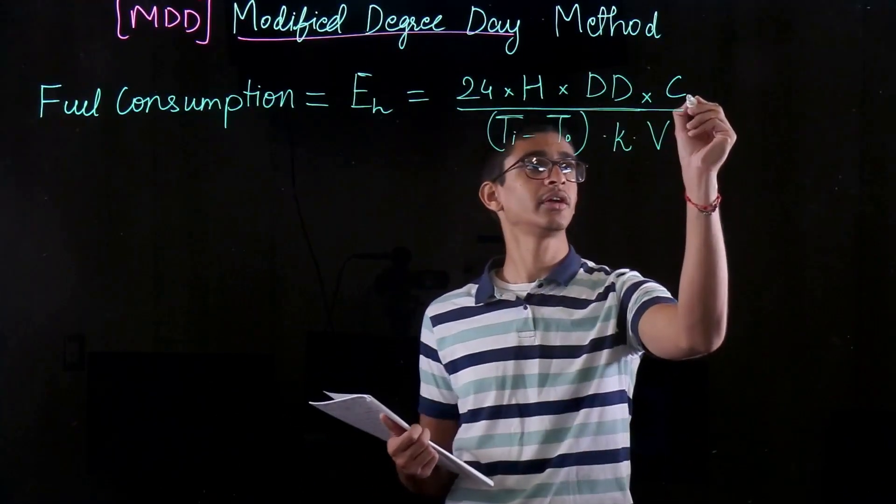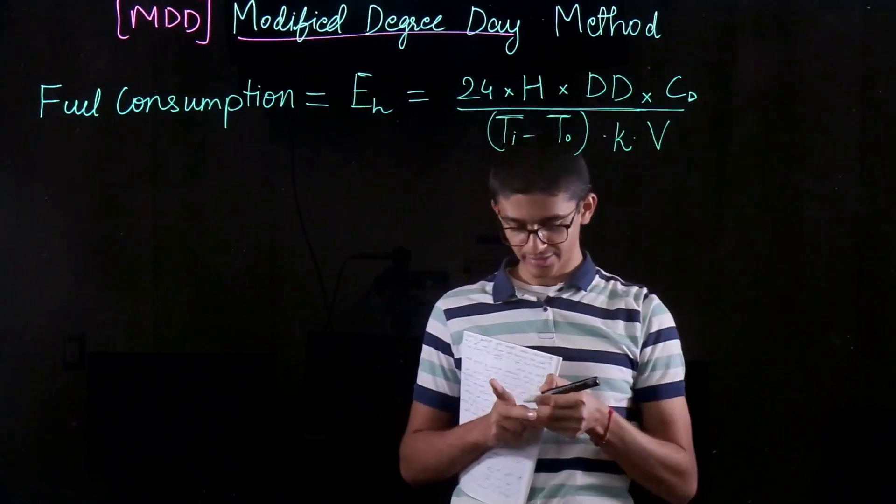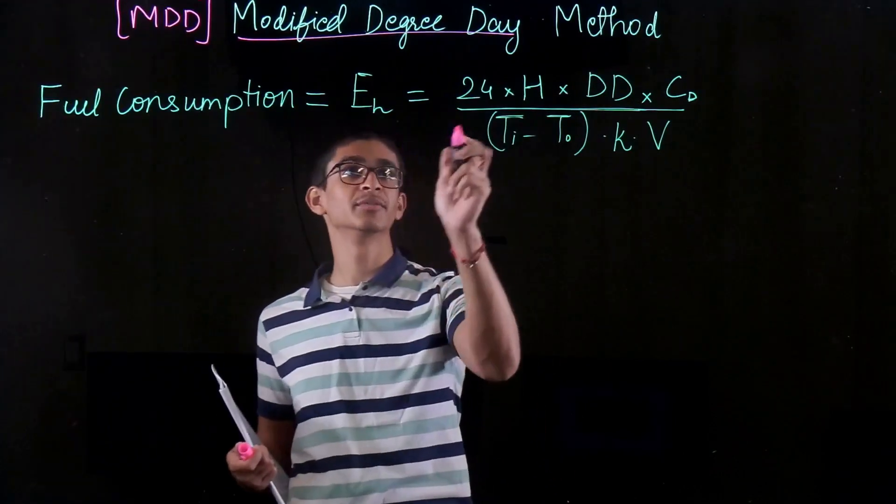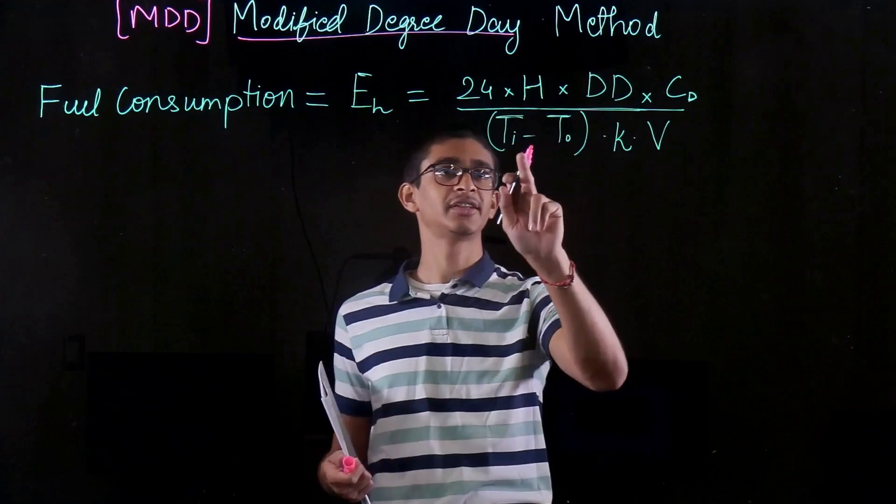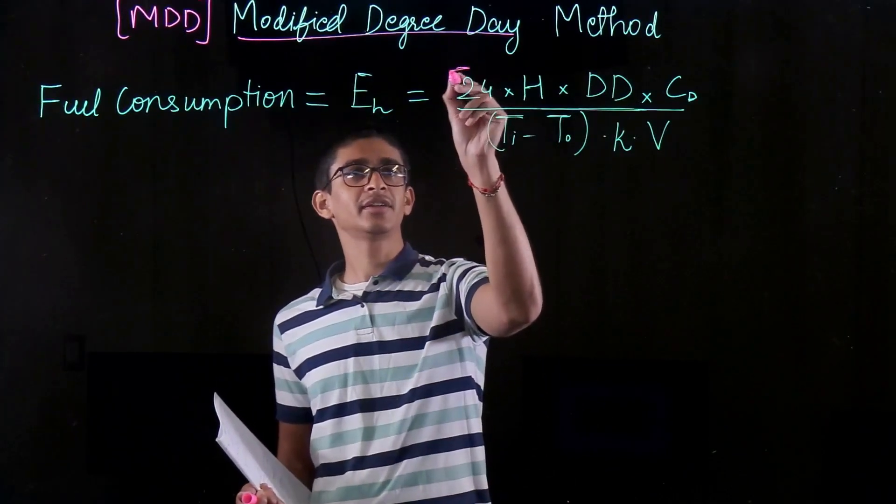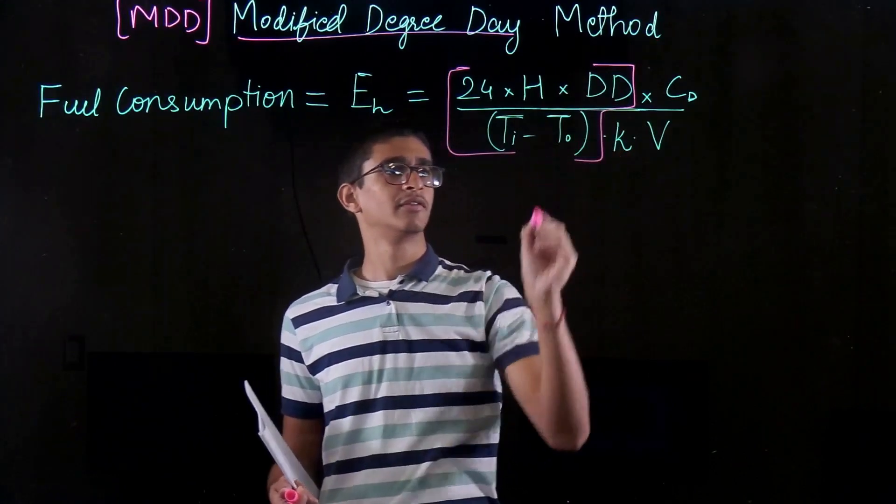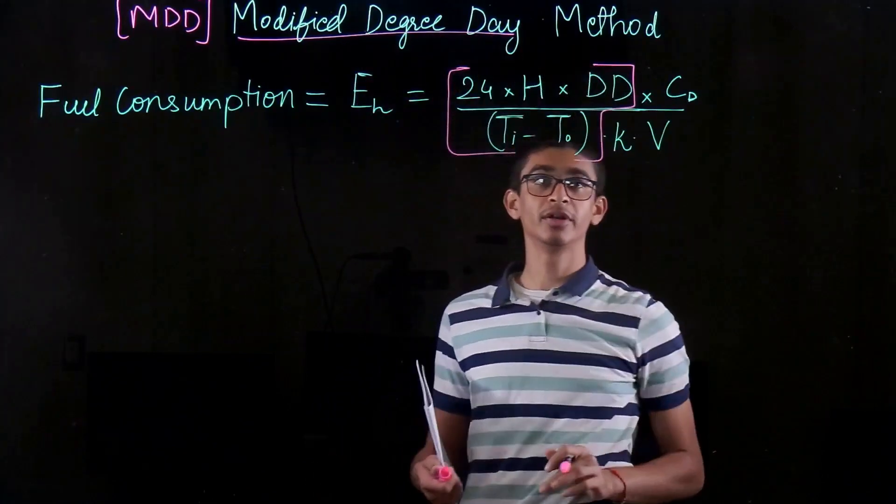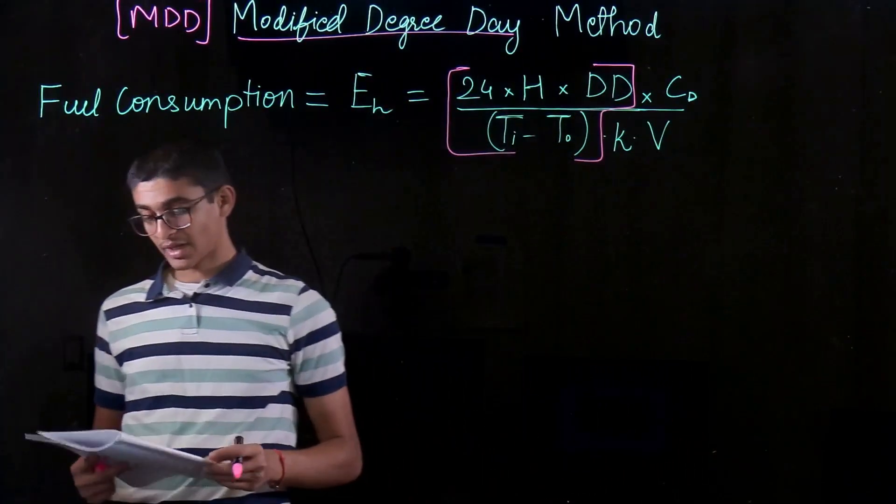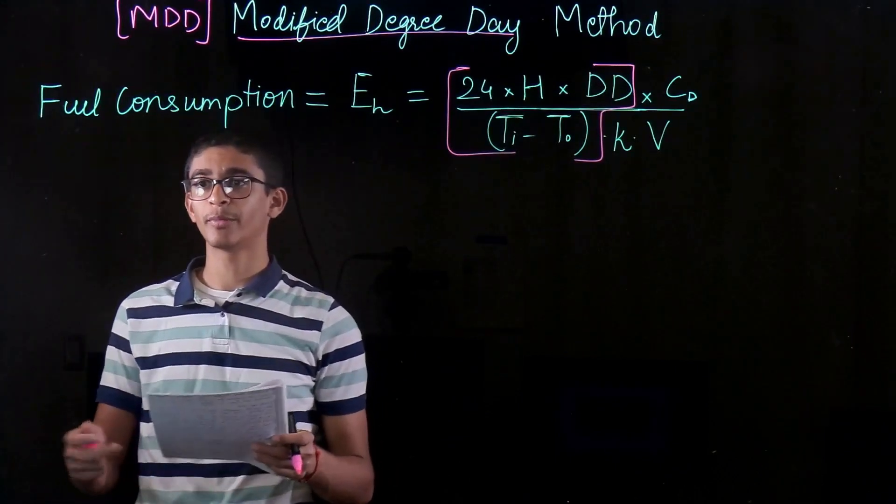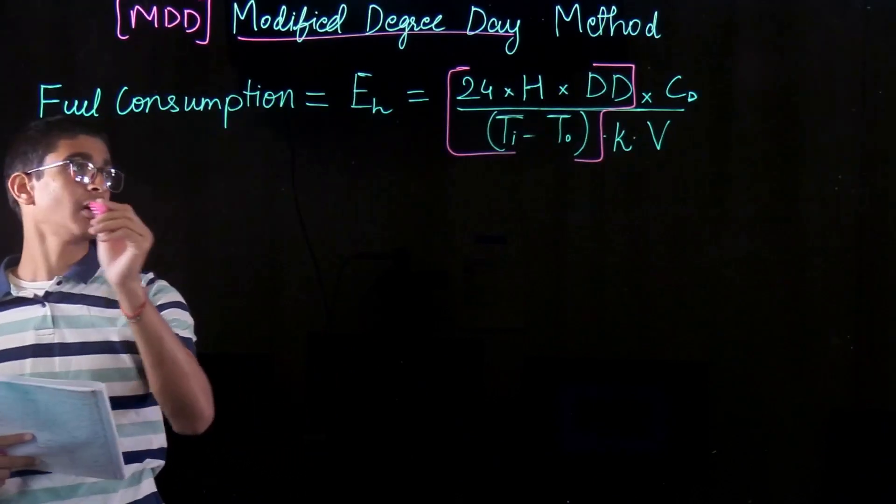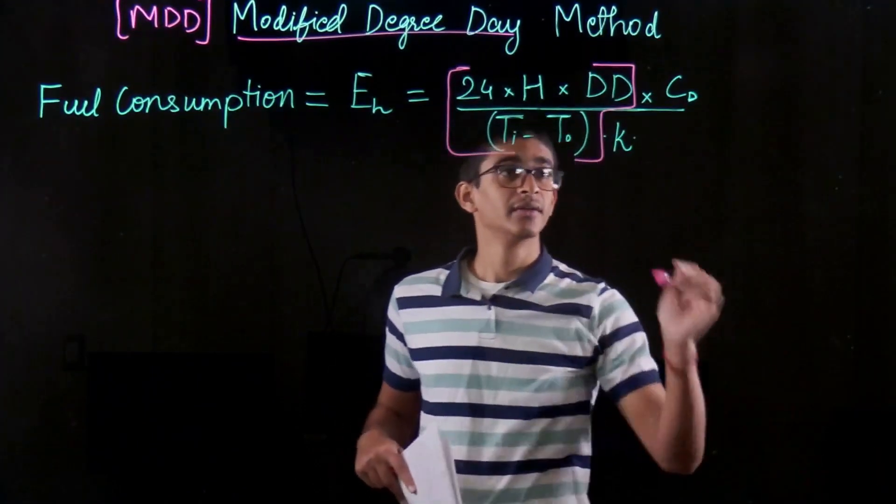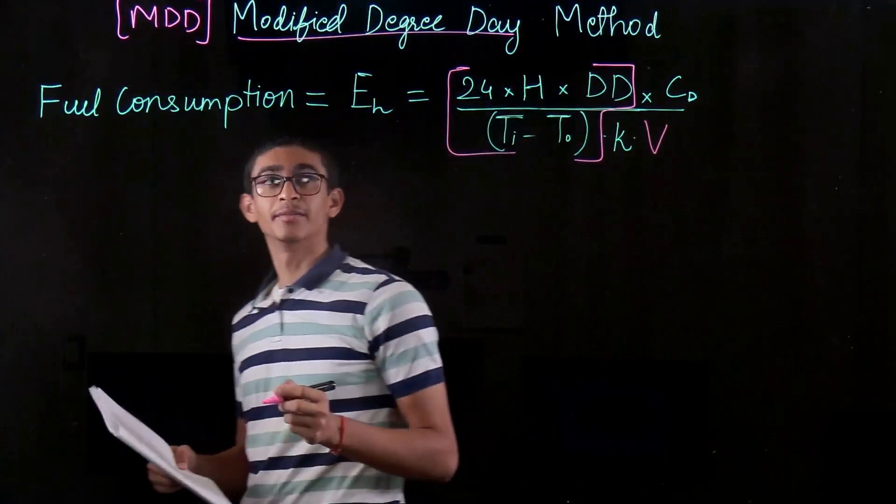So let's look at each of these factors again in detail. I hope you remember the formula for degree day method in which my fuel consumption was given by 24H into degree days divided by TI minus T out. So these many factors were the same. Three new factors have been introduced in fuel consumption estimate based on modified degree day method. V was there in the previous one also.